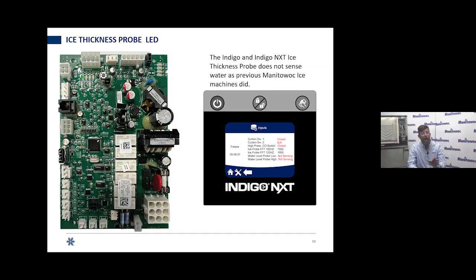What you want to use is what we're going to show here in a second. Assuming that you have a functioning display, you want to go menu, service, data, real-time data, and then inputs, because again, the ice probe plugs into the board. It is an input device. So at that point, you want to look at the 100 hertz and 120 hertz FFT ratings. As the ice starts to form, those numbers will climb. If you were doing a tap test, as we've taught in our field schools, factory schools, and on our online trainings that you've seen before, you would start with no ice on the plate. You should see those numbers lower, and as you scratch on the bump of that ice probe, they need to climb. If they climb, the probe can hear, and the board can recognize what the probe is telling it. Do not utilize that light to troubleshoot the ice thickness control probe on an Indigo or an Indigo NXT.